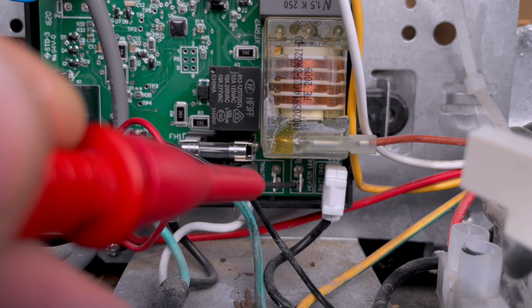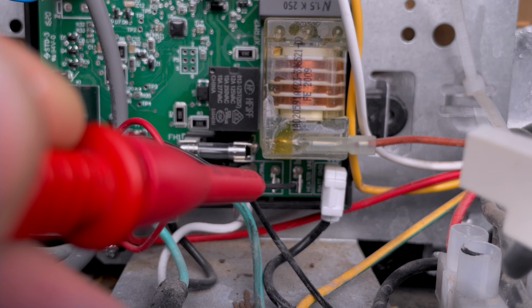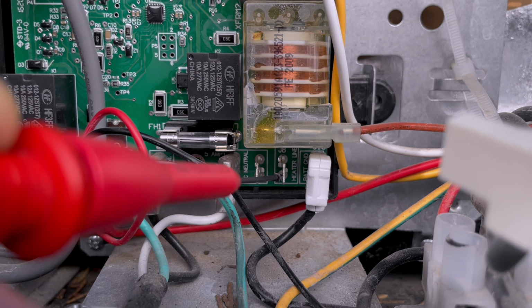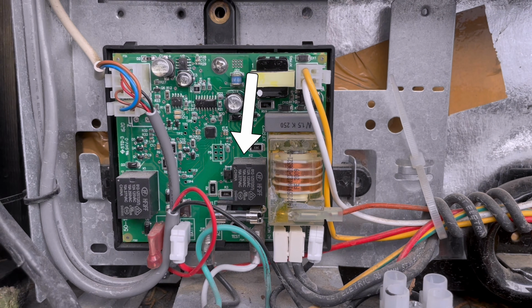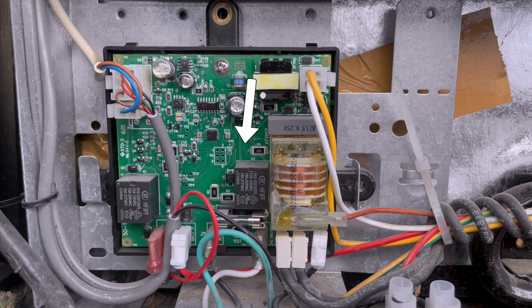If we do not see 120 on that pin, then the circuit board is most likely your problem. There's actually a relay right here on the circuit board. This relay is looking to see if you have 12 volts on that black wire that we tested earlier, then it's going to close and allow 120 volts through.